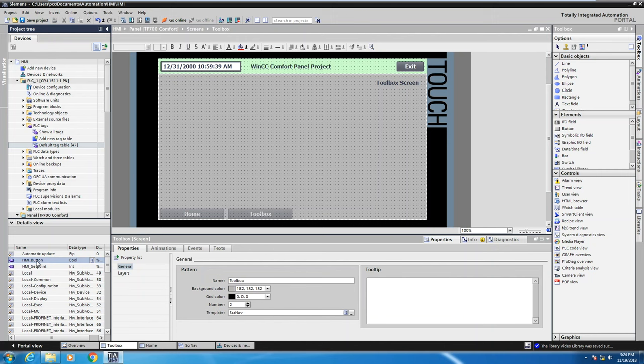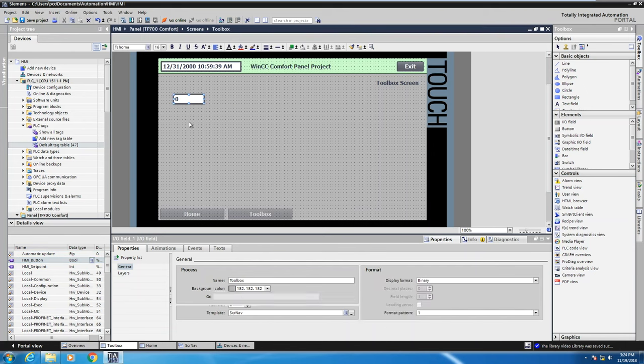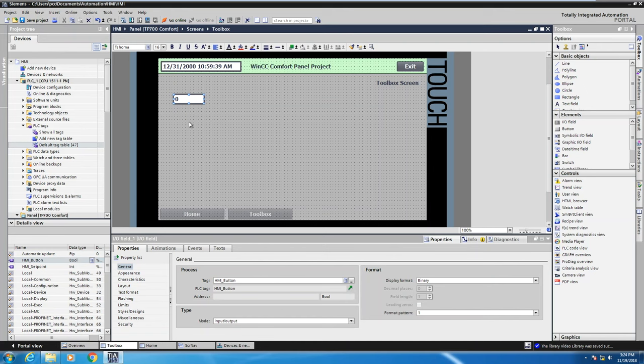So I have a tag in my PLC that's called HMI underscore button. If I drag that onto my toolbox screen, just by doing that drag and drop of dragging the tag from the PLC onto my HMI screen, that is going to create a connection between the PLC and the HMI.